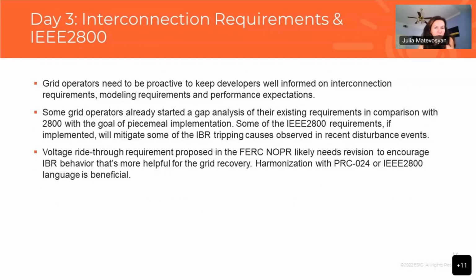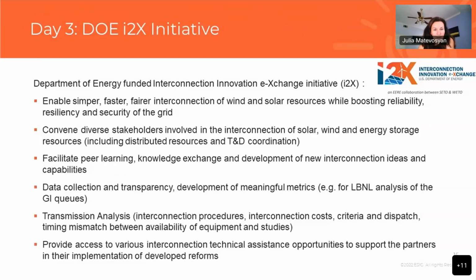Also, grid operators need to be proactive to keep developers well informed on interconnection requirements, modeling requirements, and performance expectations. Some grid operators already started gap analysis of their requirements versus 2800 and also developing a path forward with implementing those requirements. And the voltage ride-through requirement proposed in the FERC NOPR likely needs some revision to encourage IBR behavior that's more helpful for grid recovery. Harmonization with PRC-024 and IEEE 2800 language would be beneficial here. So you heard about the I2X initiative last, so I will not go through these bullet points, but you can read them if you look at the slides again.